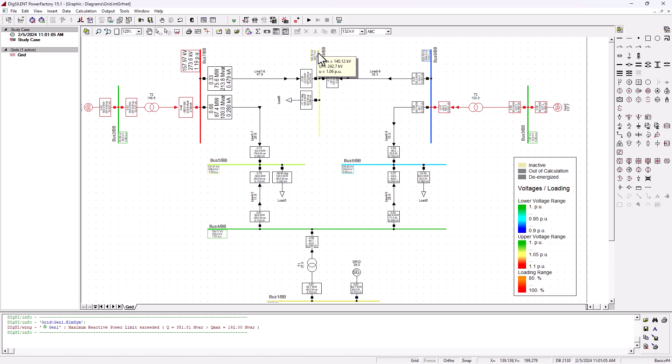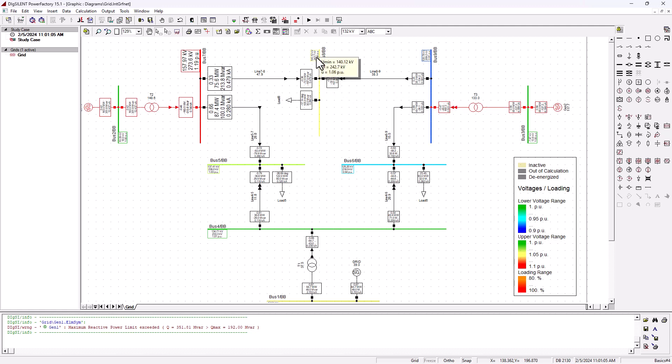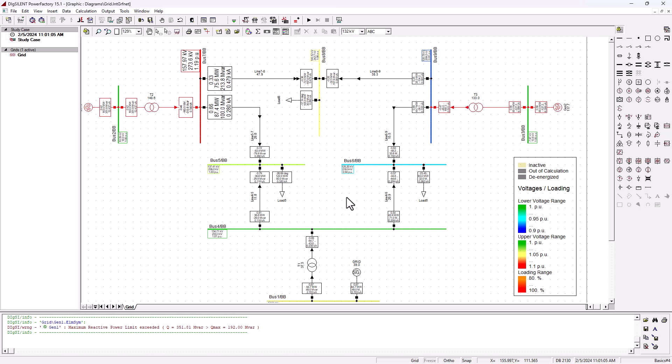When we zoom into the bus bar parameters, we can see that the nominal per unit voltage is one point zero six per unit, and in terms of voltage is two four two point seven kilovolts. Remember, this bus bar is supposed to be running on the transmission line that is rated at two thirty kilovolt. But we are sitting with a voltage of two forty two point seven kilovolts, which is definitely higher than what it was specced for.